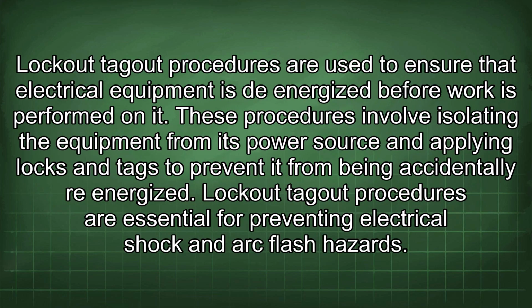Lockout-tagout procedures are used to ensure that electrical equipment is de-energized before work is performed on it. These procedures involve isolating the equipment from its power source and applying locks and tags to prevent it from being accidentally re-energized. Lockout-tagout procedures are essential for preventing electrical shock and arc flash hazards.